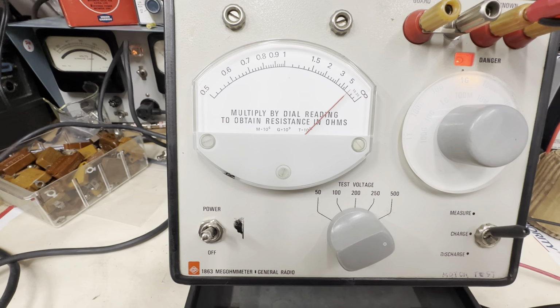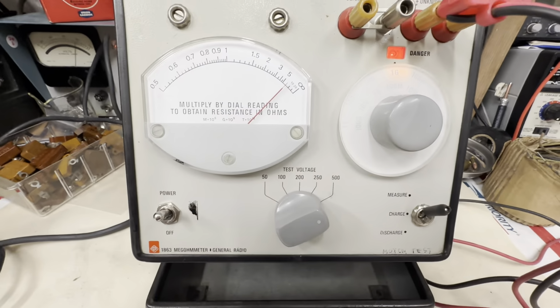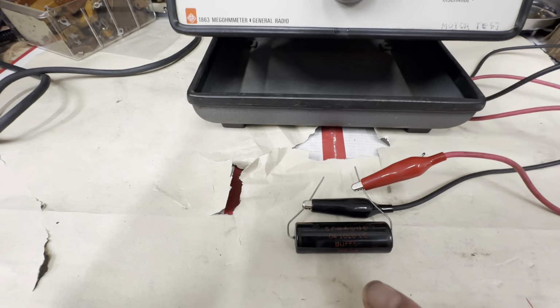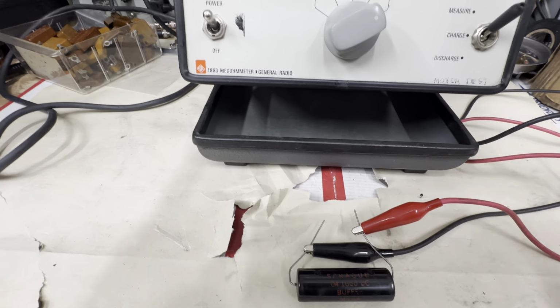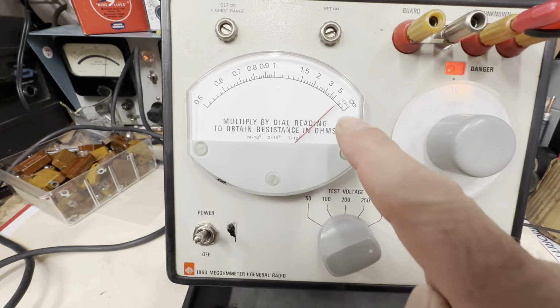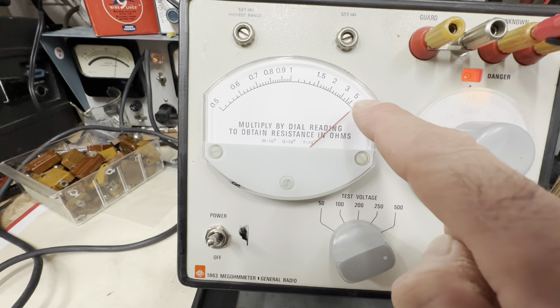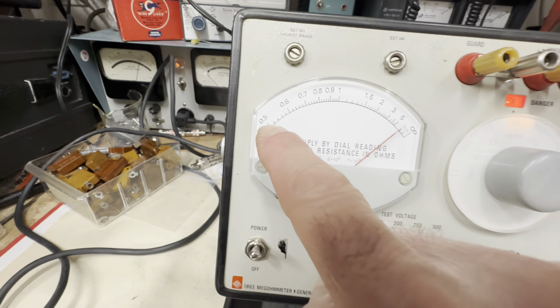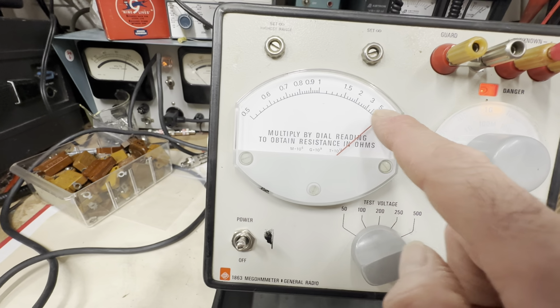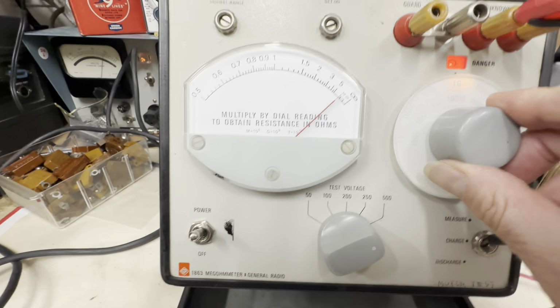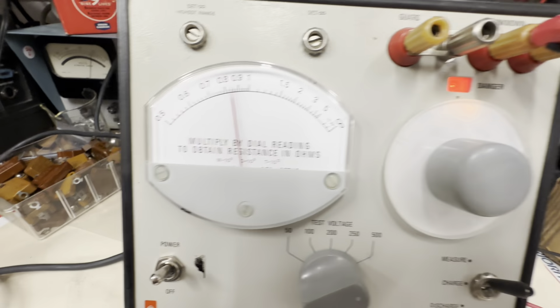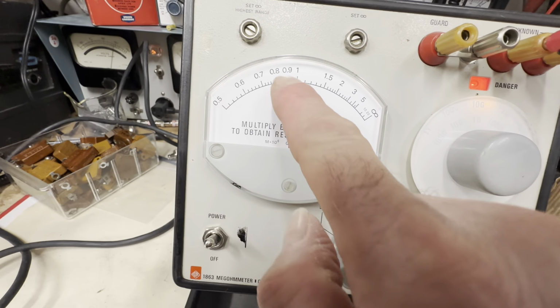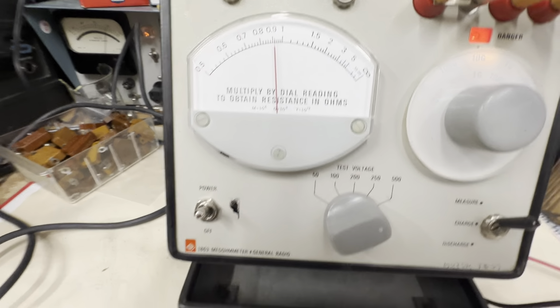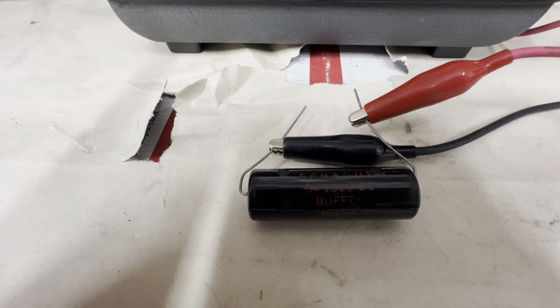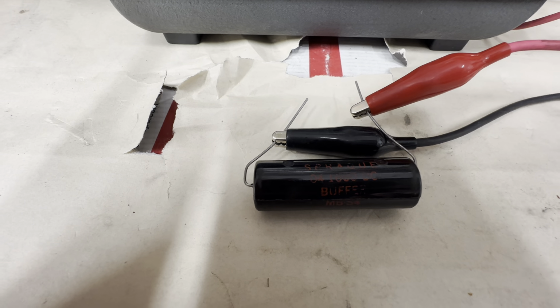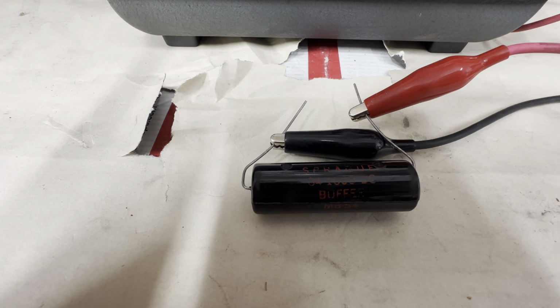The important thing is, though, that at 1 gig ohm plus with 500 volts on it, this capacitor works. And that's all we need to know right there. We can actually kick this up to the next scale. If you look, we're more than 5, and if you see the scale over here, it starts at 0.5. So if we kick the next scale up, it'll be 0.5 plus something. Let's go to the 10 gig scale. There's 10 gig, and oh boy, look at that. Right now we're at 9 gig and counting. So we're going to call this capacitor good, at least as far as leakage goes. Let's go to another capacitor.